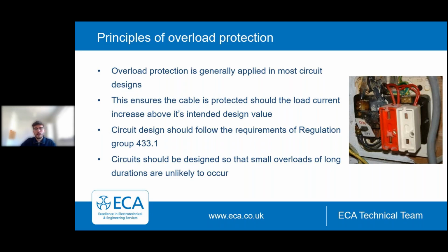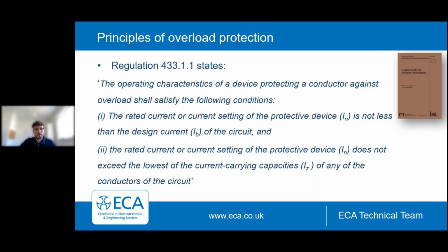And Regulation 433.1.1 looks at coordination between conductor and overload protective devices, and it initially provides us with three indents. But I'm initially going to run through the start of the regulation and indents 1 and 2 to start with.